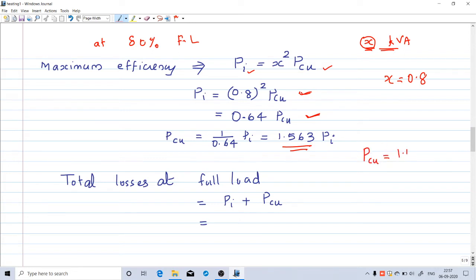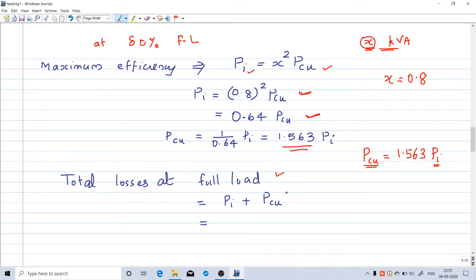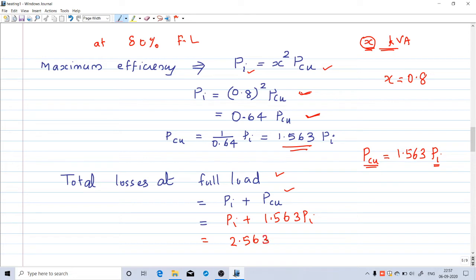The total loss at full load is iron loss plus full-load copper loss: pi plus pcu. Since pcu equals 1.563 pi, total losses equal pi plus 1.563 pi, which equals 2.563 pi. So the total losses in the 400 kVA transformer equal 2.563 times iron loss.